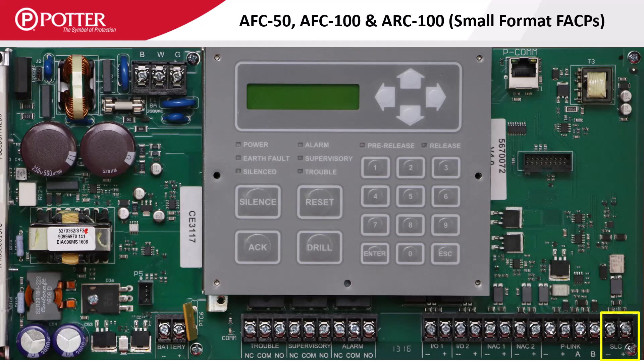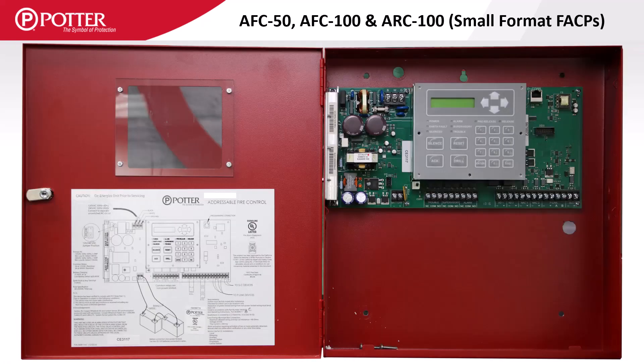There is a significant difference in the LCD display size, as the smaller panels only have a two-line by 16-character display. In the top right corner is the P-COMM port. In the enclosure for the small format panels there is no space for stacker bracket accessory cards, so an accessory enclosure is required when installing these cards on a smaller format panel.